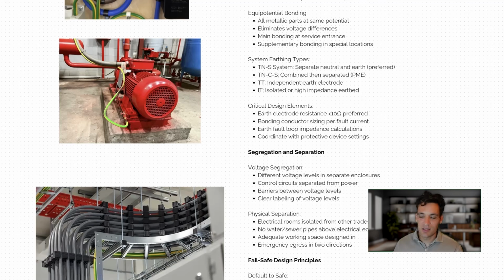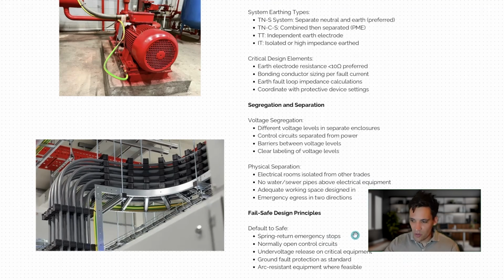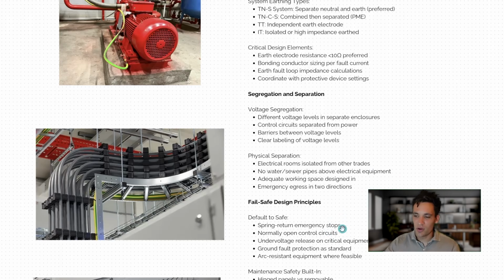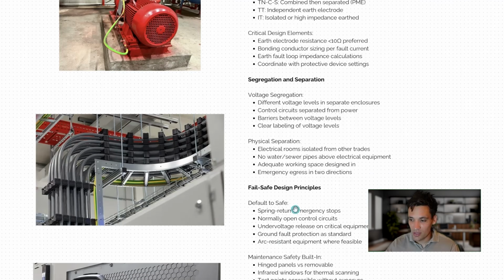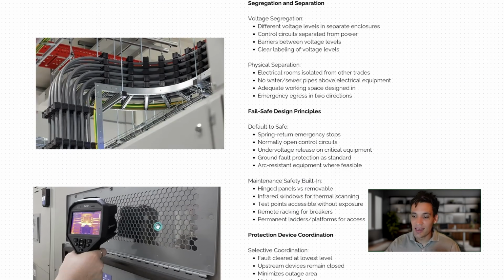Basically, you're trying to set up a situation where people can safely work on a system and not have to interact with that other system whatsoever. All the equipment should default to safe operation. If something's wrong, for example a circuit breaker has a failure, it shouldn't fail to being closed, it should fail to being open. So everything should default to safe, and you should have maintenance.